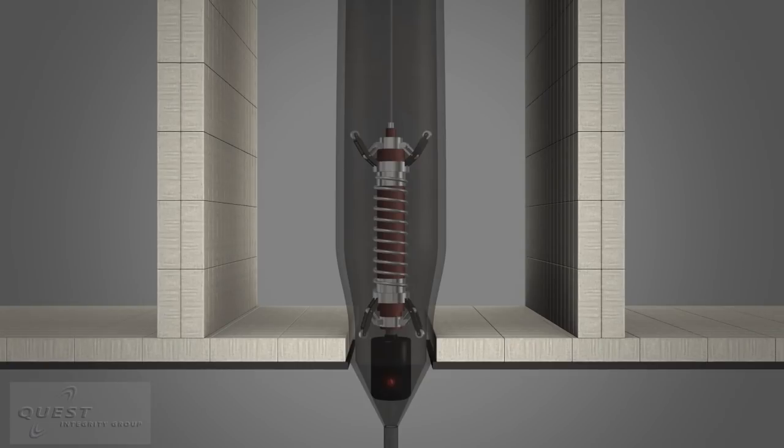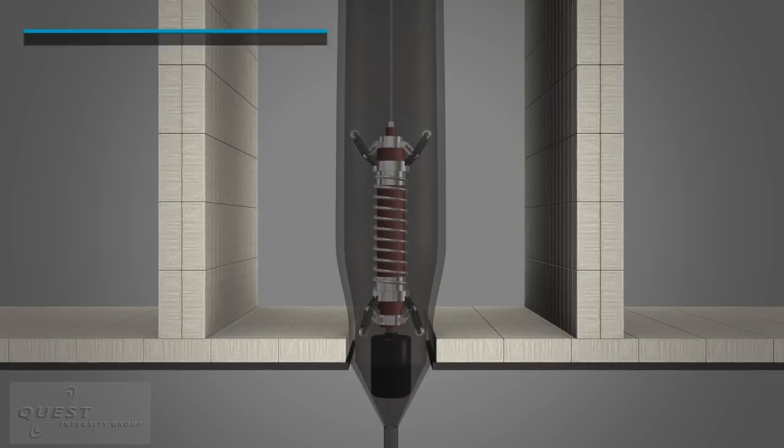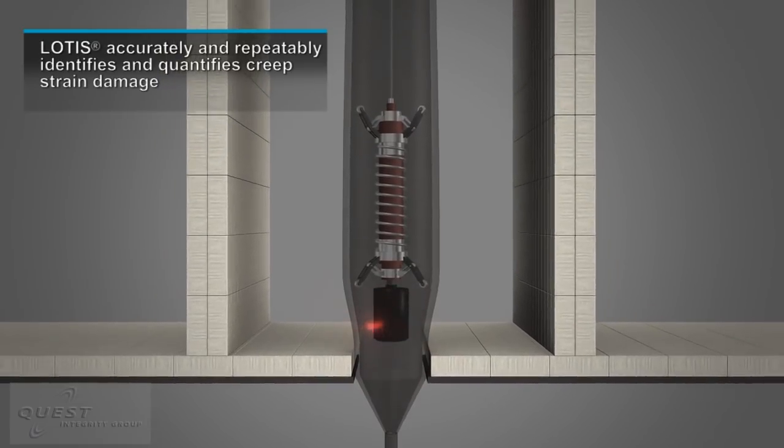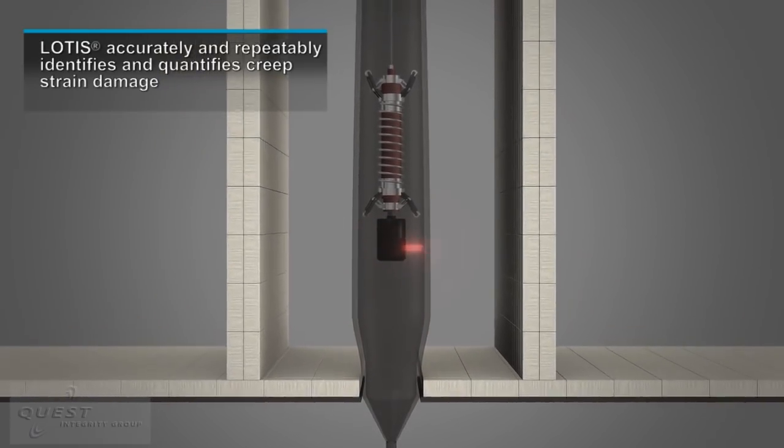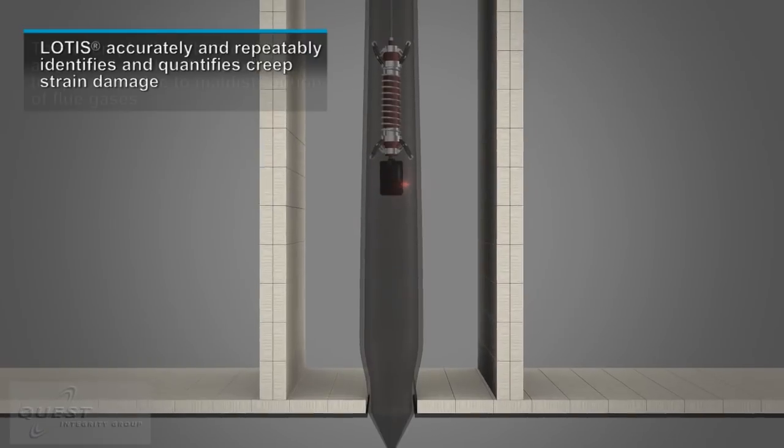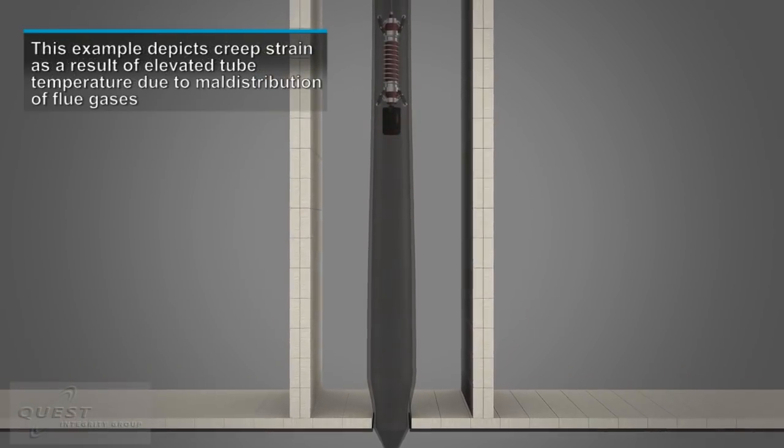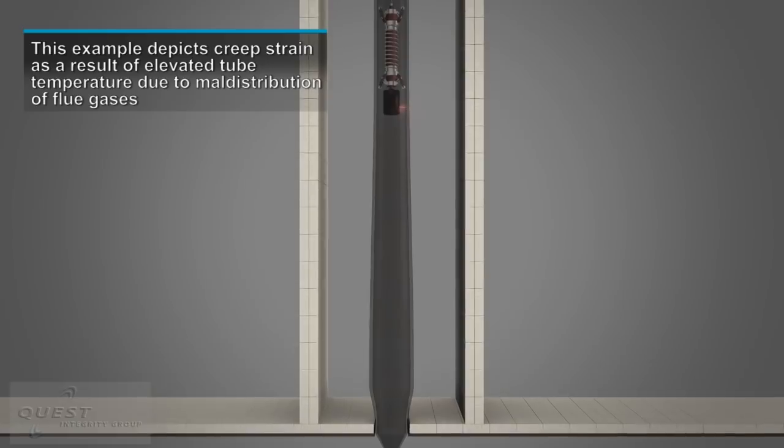The predominant failure mechanism is creep strain. LOTIS detects and quantifies creep strain damage caused by excessive temperature and pressures during operation. The rate of this damage mechanism is a function of exposure time at elevated temperature and the applied structural load.